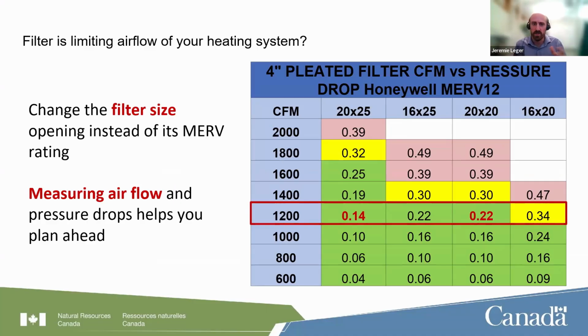I have a table here just to show you what that can mean in terms of pressure drop. We have different filter sizes. This is for a 4-inch pleated MERV 12 filter, and as we walk down the rows, we have different airflows going through this filter. Let's say we had an existing filter cabinet or filter slot with a 20 by 20 opening. We're generating about 0.22 inches of water of pressure drop through that filter. Moving to a larger filter size, a 20 by 25 opening for example, can almost cut the pressure drop in half. So there are techniques to move to a higher MERV filter without increasing the pressure drop, but that might require a larger opening, something to look into as a design consideration.